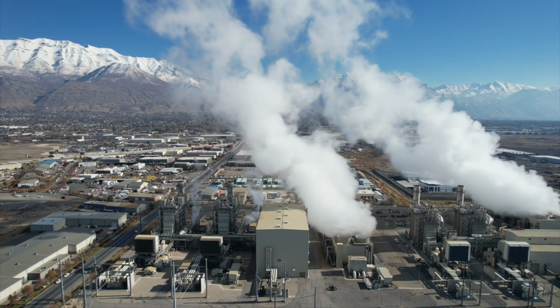Now, we will understand the performance of combined cycle power plants. The most important parameters which affect the efficiency and specific output of the simple gas turbine plant are the compressor pressure ratio and the turbine inlet temperature. The optimum pressure ratio with respect to the specific output is not the optimum one for the thermal efficiency, so the designers choose a pressure ratio which maximizes the overall economy of the plant.